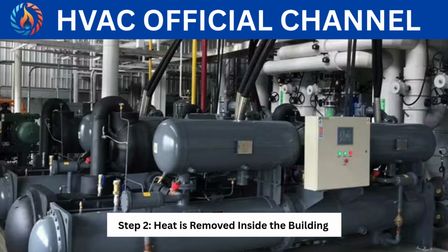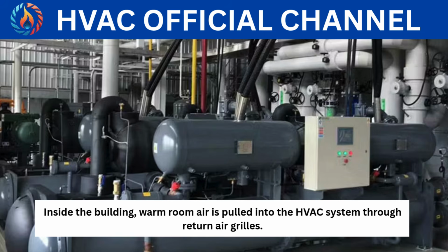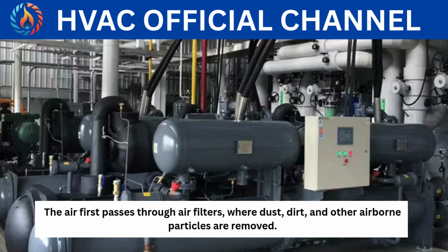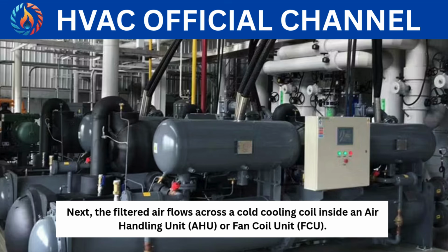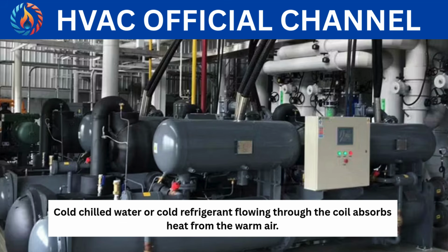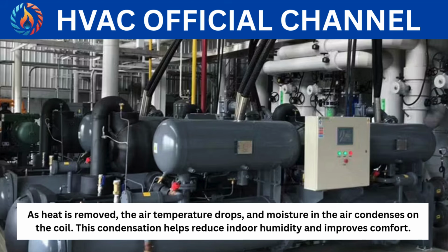Step 2. Heat is removed inside the building. Inside the building, warm room air is pulled into the HVAC system through return air grills. The air first passes through air filters, where dust, dirt, and other airborne particles are removed. Next, the filtered air flows across a cold cooling coil inside an air handling unit or fan coil unit. Cold chilled water or cold refrigerant flowing through the coil absorbs heat from the warm air. As heat is removed, the air temperature drops, and moisture in the air condenses on the coil. This condensation helps reduce indoor humidity and improves comfort.